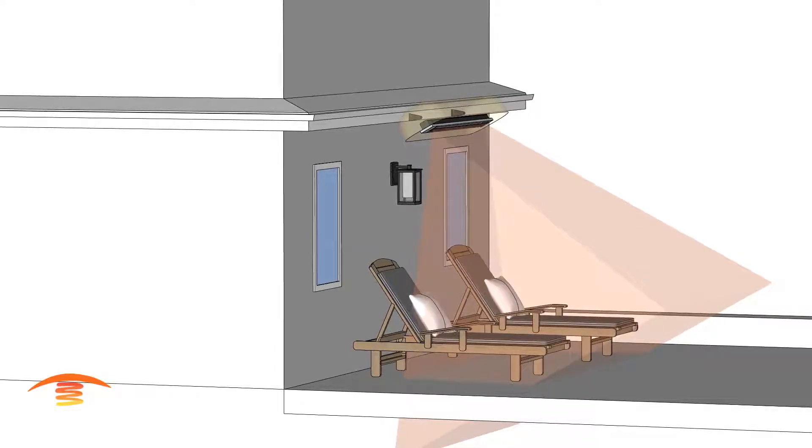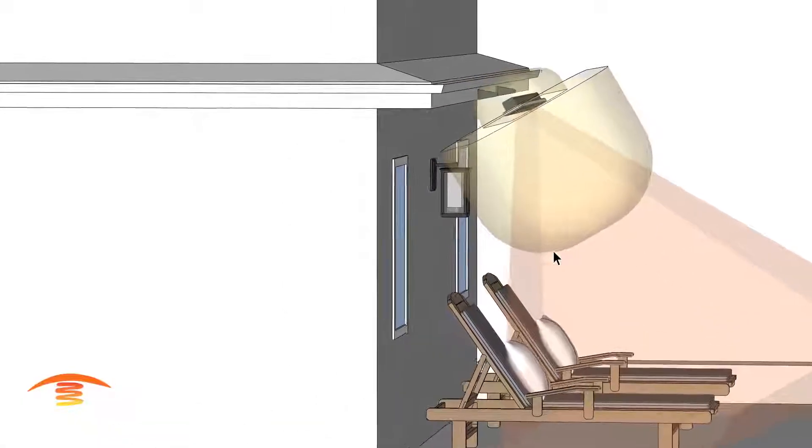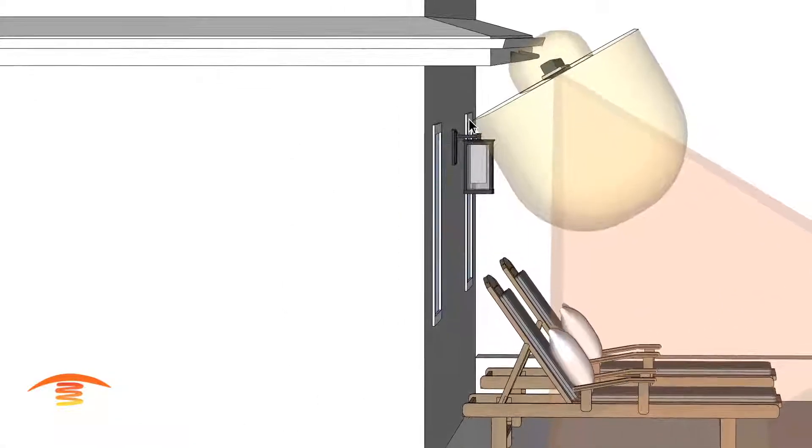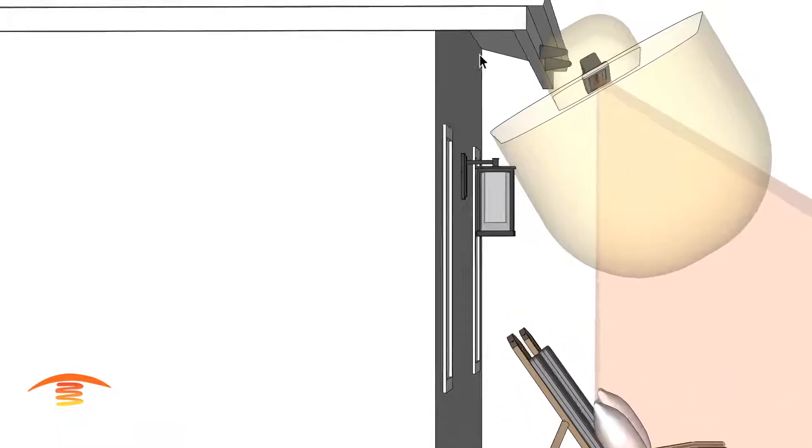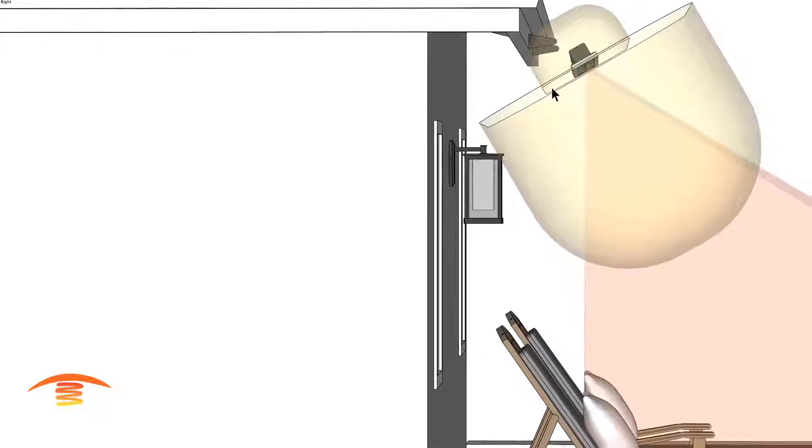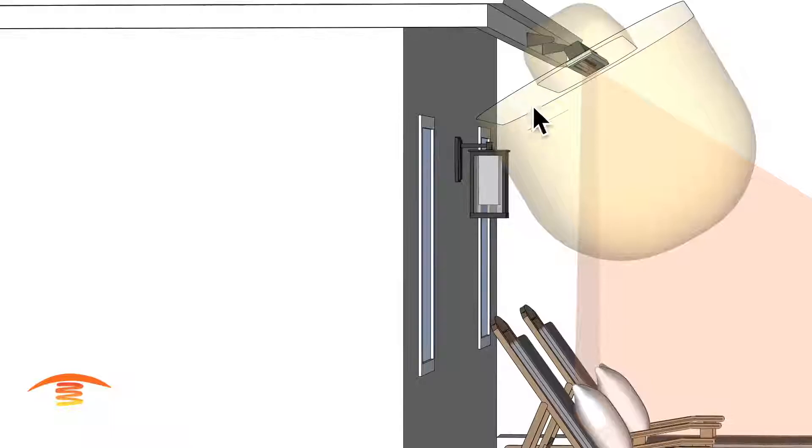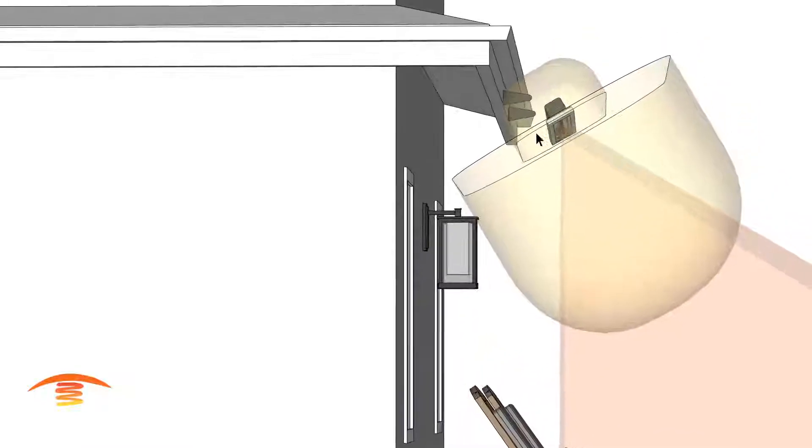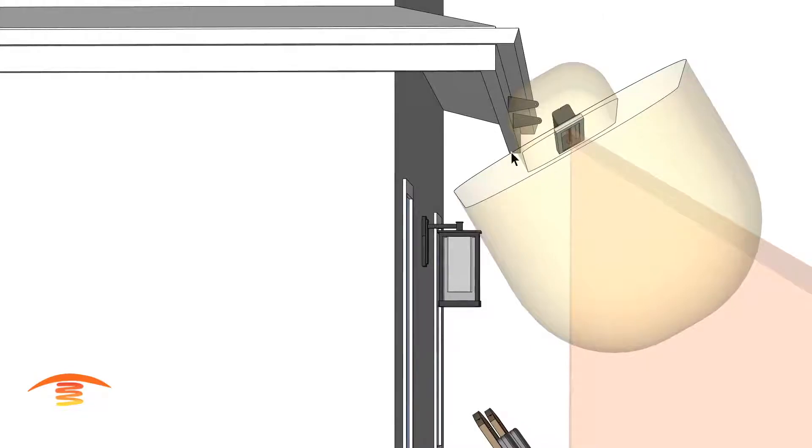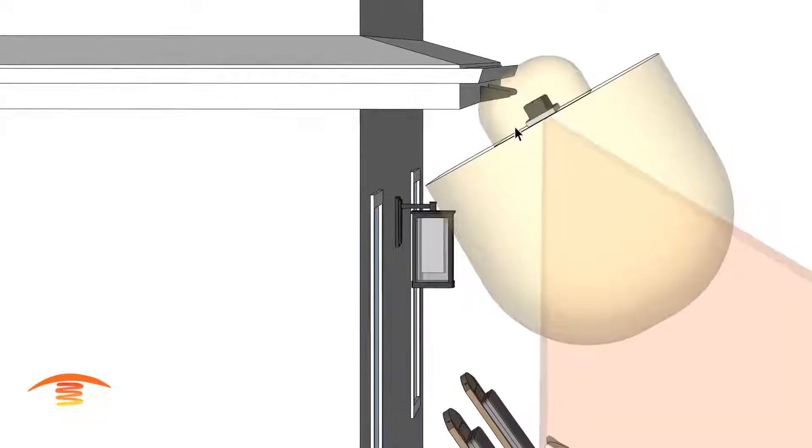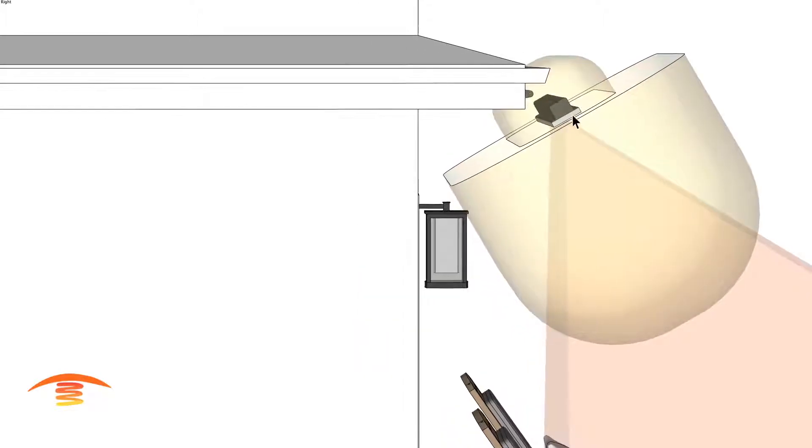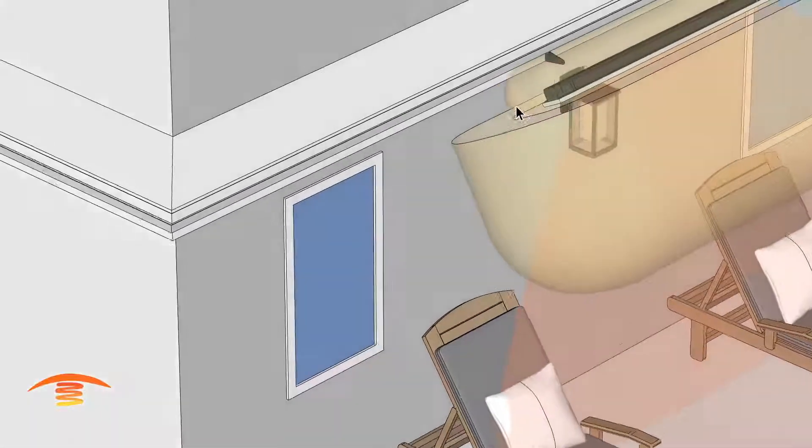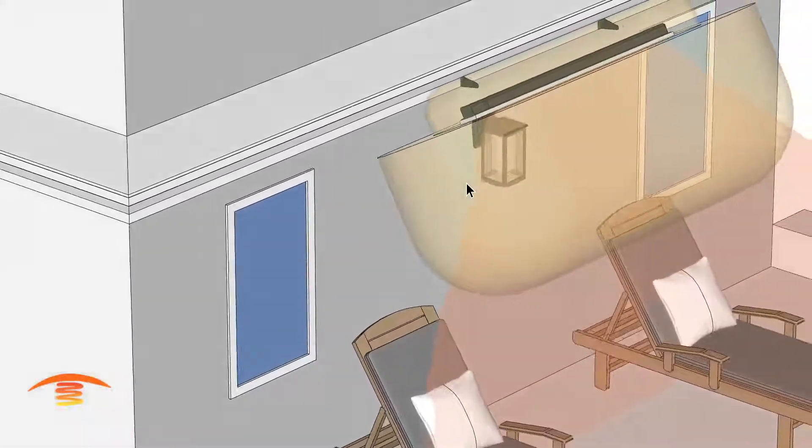And that is the clearance below the heater. This is another reason you can't just mount it even on a wall. So if I was to take this heater and try to move it to the wall surface and place it inside this cavity, then I would be not meeting the clearances over here. This is from this point here, the edge of the heater out is 18 inches. And then it goes out to 32 inches down here. This up here is from the top of the heater here, six inches. And from the sides, six inches, six inches. And from the ends, six inches on top. And of course, here's 18 on the bottom edge of that.